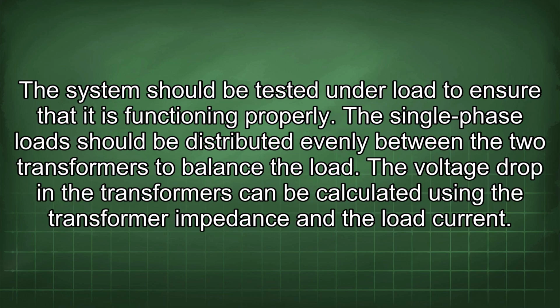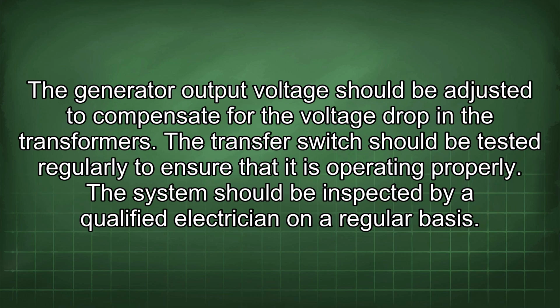The system should be tested under load to ensure that it is functioning properly. The single-phase load should be distributed evenly between the two transformers to balance the load. The voltage drop in the transformers can be calculated using the transformer impedance and the load current. The generator output voltage should be adjusted to compensate for the voltage drop in the transformers.